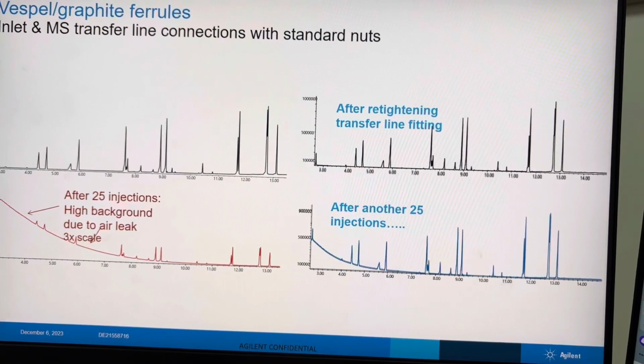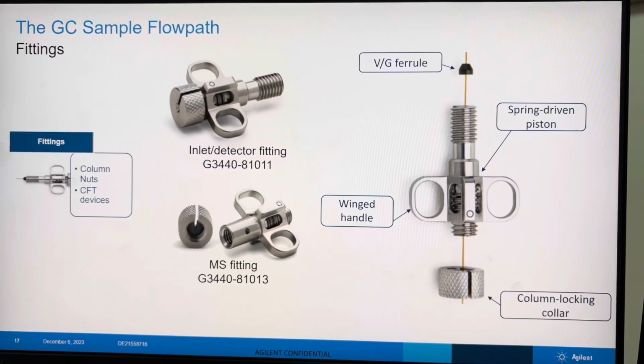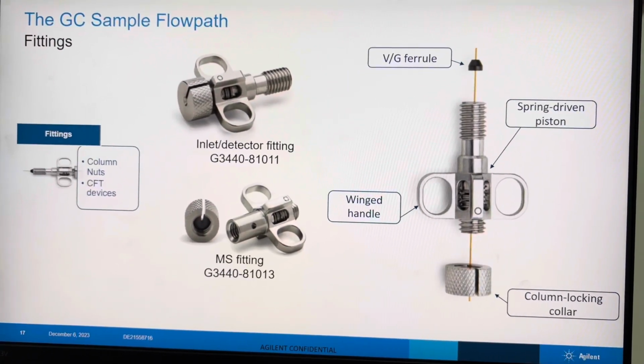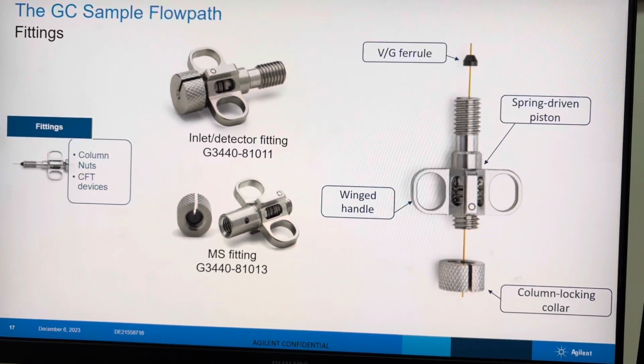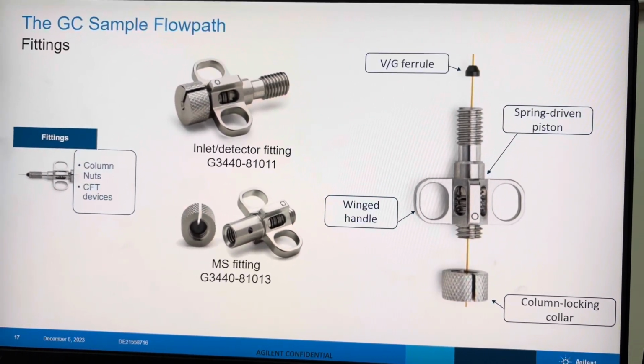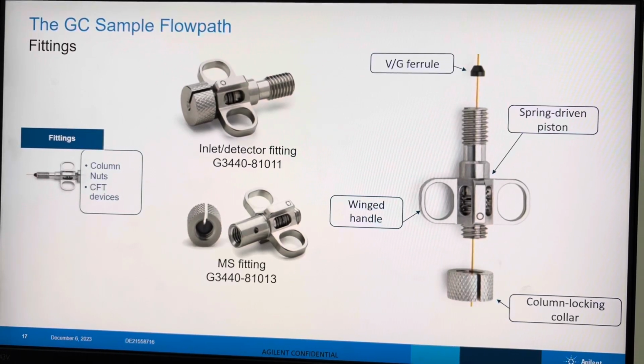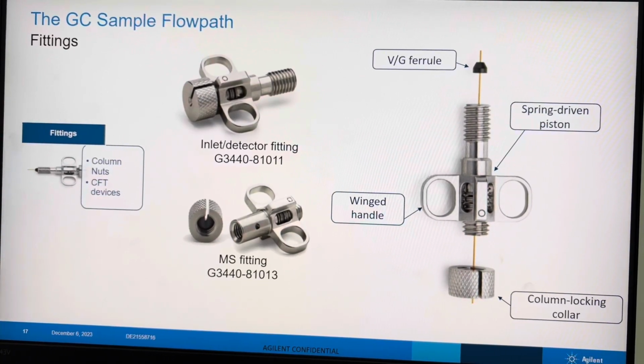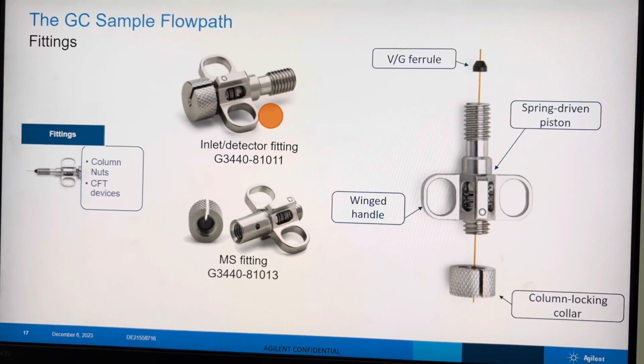And for a connection, in the traditional way, it is really difficult for us, with all the tightening and retightening, we need to be careful. That is where self-tightening nuts came. The nuts have grooves, and we can do it with our hand and with a collar.